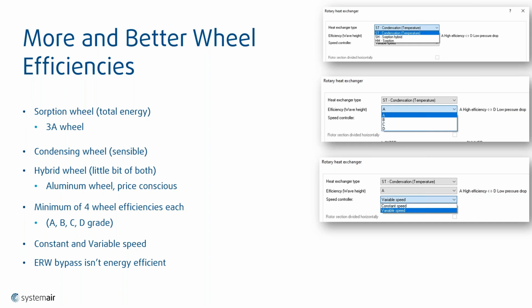Having said that, when you're designing a project, and the reason that we give you all these options is that you could get an efficiency as high as 83 or 84% on a wheel, but nothing in life is free. So once you're getting those high efficiencies, your pressure drops through the units are exceptionally high. You might not require 83%, you might only need 75%. So you would be able to reduce your efficiency maybe down to a class B or a C or even a D, and then have less pressure drop through the actual unit, which means that your fans don't use as much energy as well.